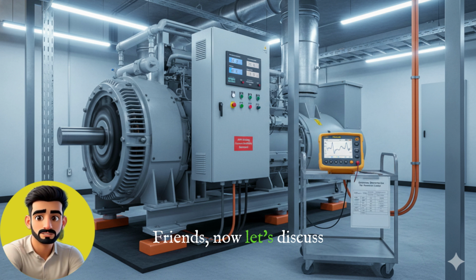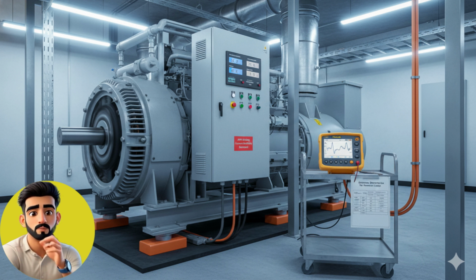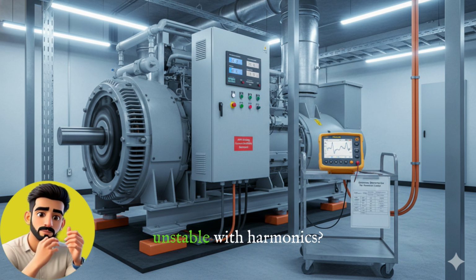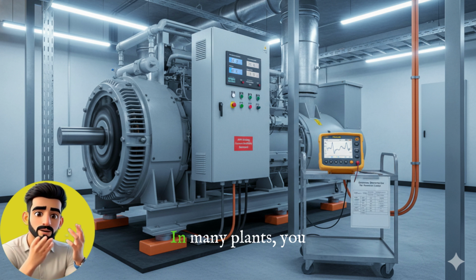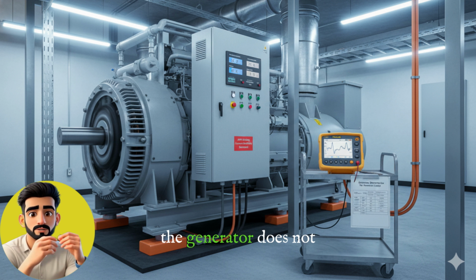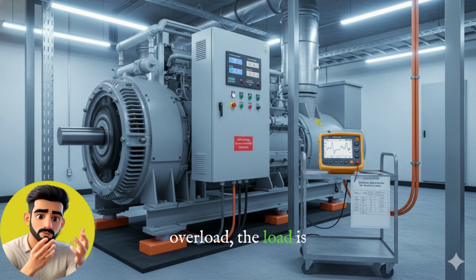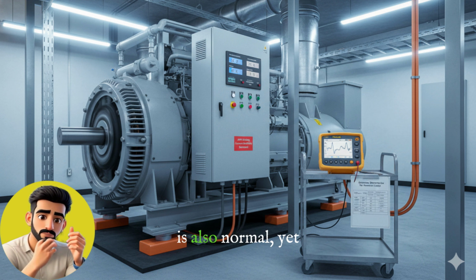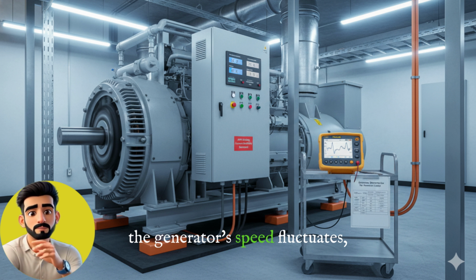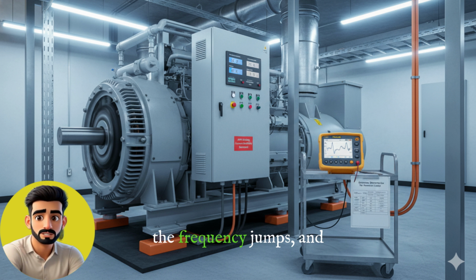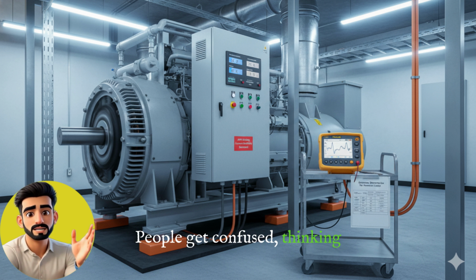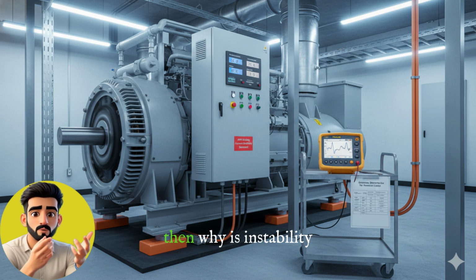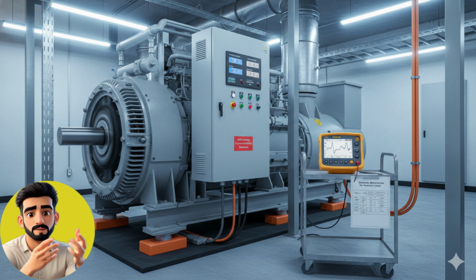Friends, now let's discuss another important topic. Why do generators become unstable with harmonics? In many plants, you might have seen that the generator does not overload. The load is only half. The voltage is also normal, yet the generator's speed fluctuates. The frequency jumps, and the automatic voltage regulator keeps adjusting repeatedly. People get confused thinking the load is low. Then why is instability occurring? The simplest reason for this is harmonics.